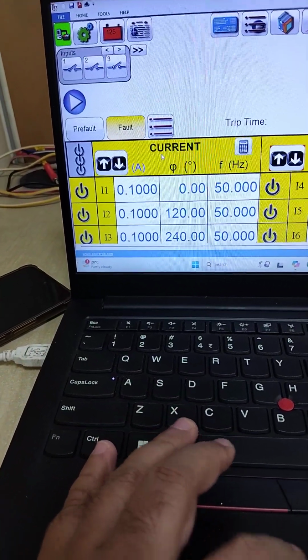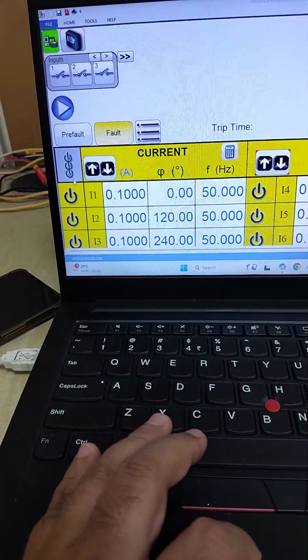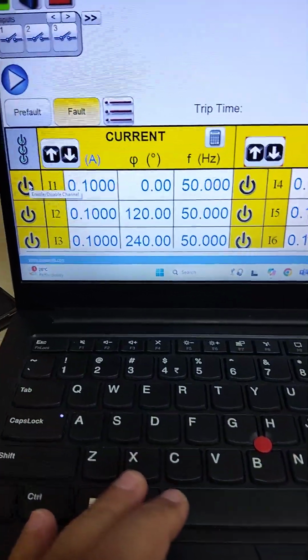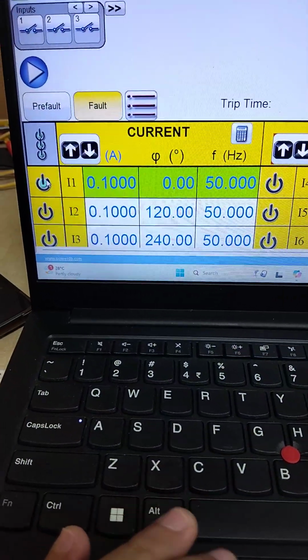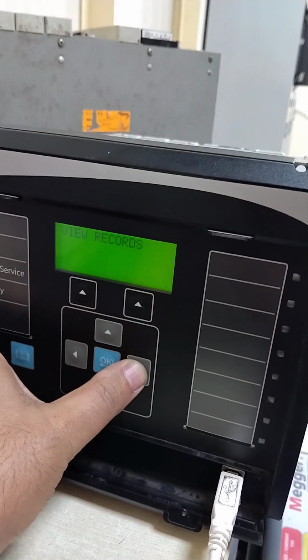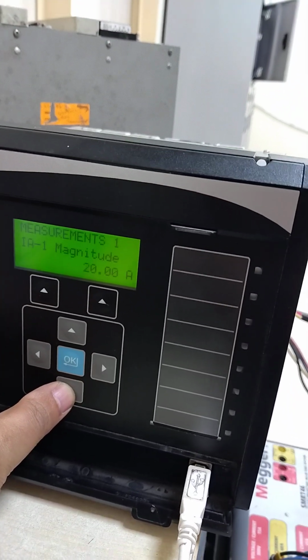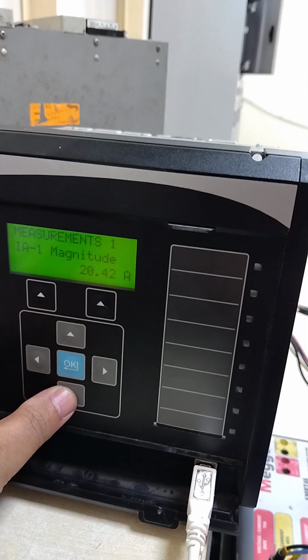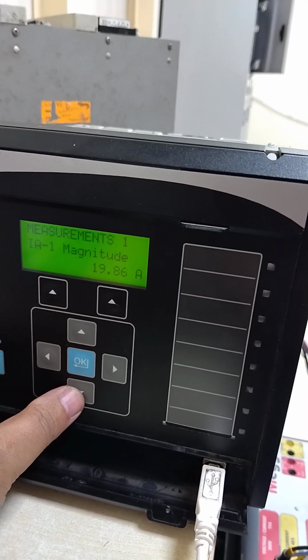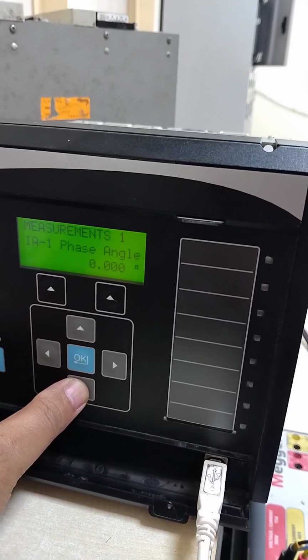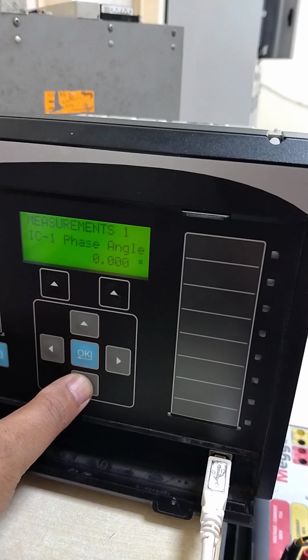Inject 0.1 ampere on all, enable it, and inject only on the HV side R phase. So I only injected 0.1 ampere on the HV side of R phase. Here you can see that 200 is my CT ratio, so I have injected 10%, so I am getting 20 amperes. On other phases the current is 0.